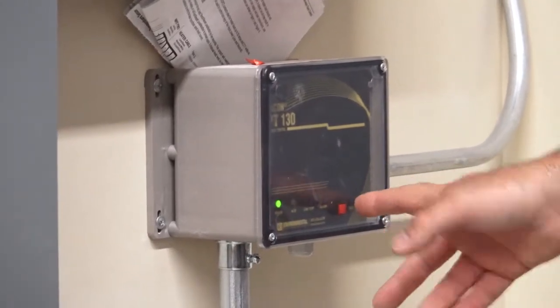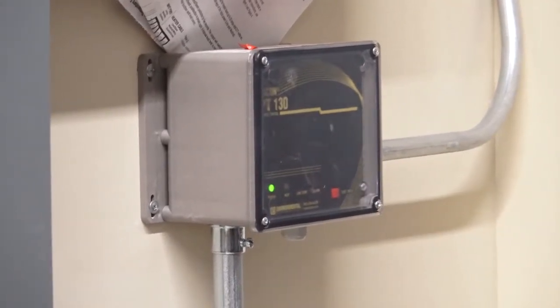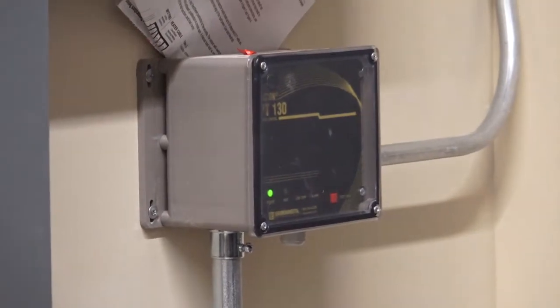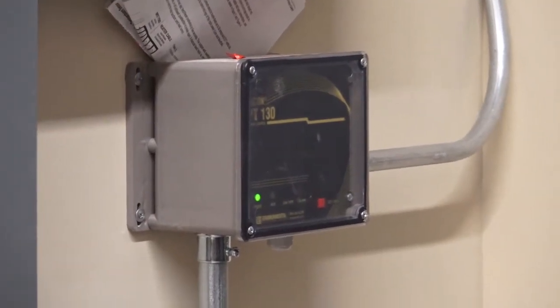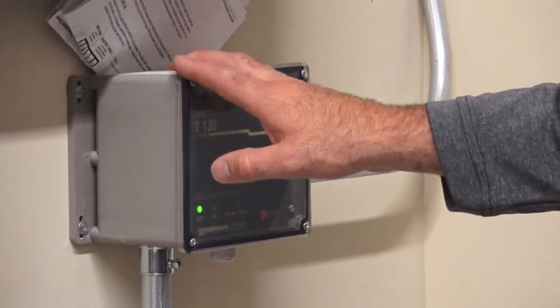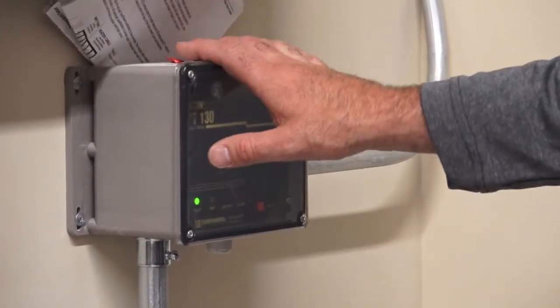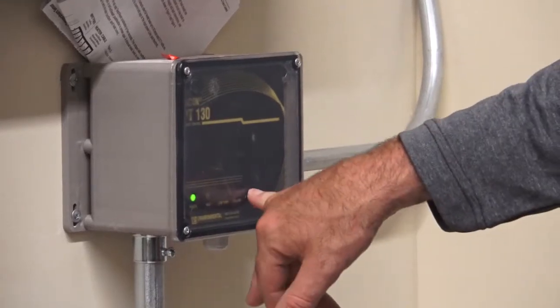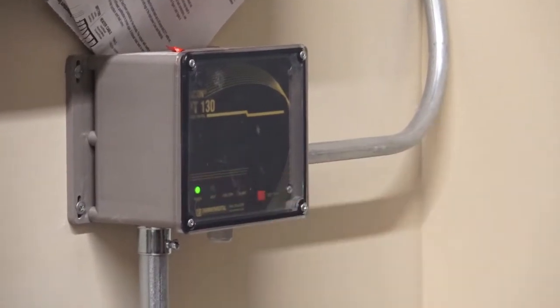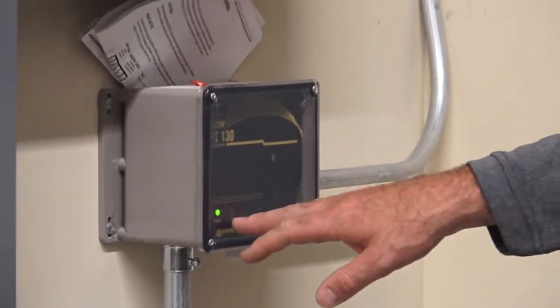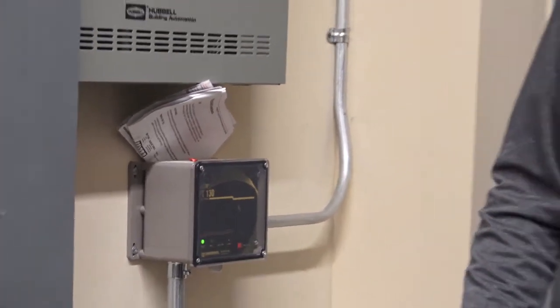If you want to hit the test button, test it once a year. That basically tests for a ground fault, to see if there'd be a short or something, and make sure it would shut itself off. If there's a fault out there, this is supposed to shut itself off and the alarm lights will come on. I'd just check on this before every winter, at least look at how the lights are and what the status is.